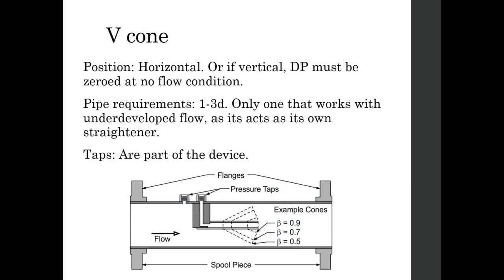For V-cone installation: position horizontal, or if vertical the differential pressure must be zeroed on a no-flow condition — though that's standard for all these elements. Piping requirements are only 1 to 3 diameters upstream, and it is the only element that works with underdeveloped flow. It essentially acts as its own straightener because the cone inside the piping pushes the flow where it needs to go. The taps are part of the spool itself: the low pressure side is attached to the end of the cone, and the high pressure side is on the upstream side.